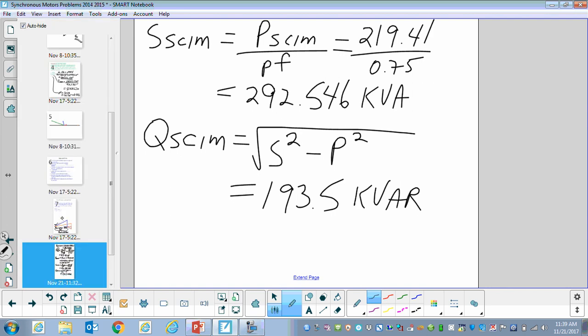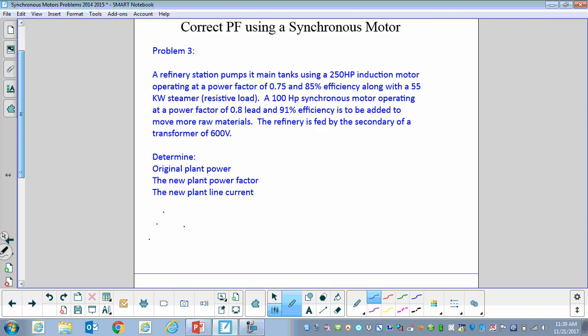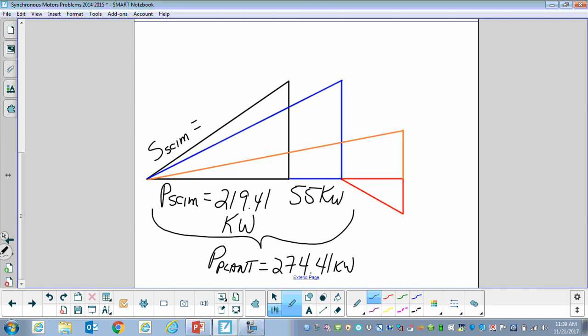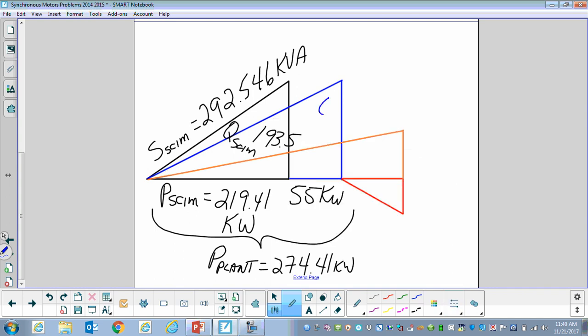So we'll go back to our triangles. Two values we can put in are 292.546 for S and 193.5 for Q of the squirrel cage induction motor. Since Q is 193.5 for the squirrel cage induction motor, we also know that's the same value for the plant. So Q plant is 193.5 kVARs. We're going to need that here in a little bit.